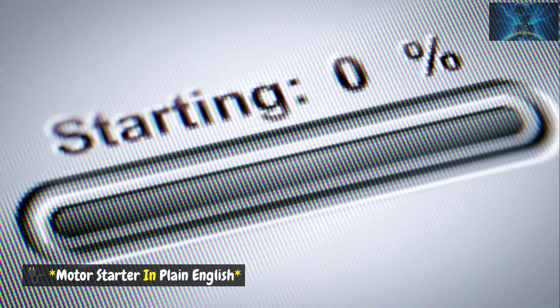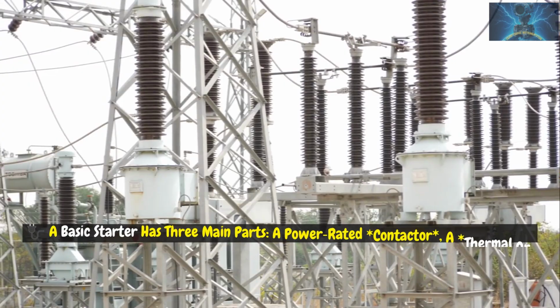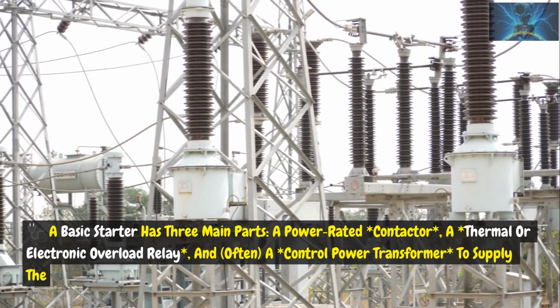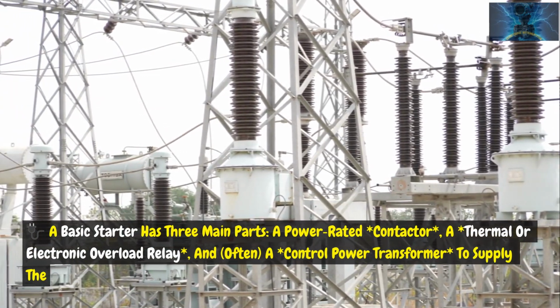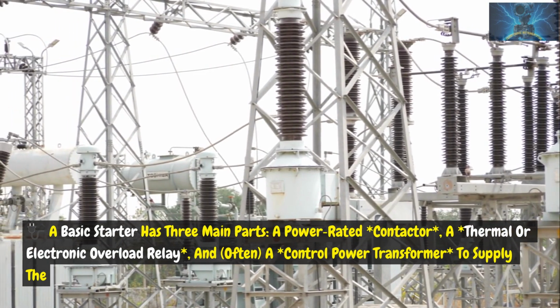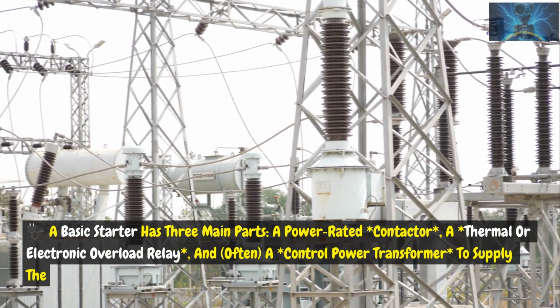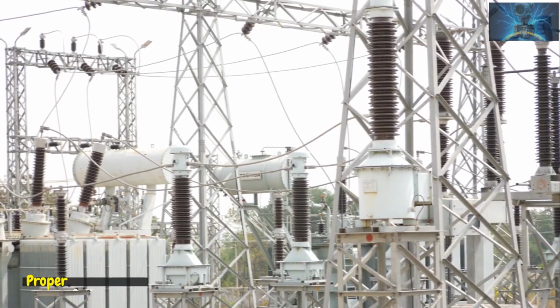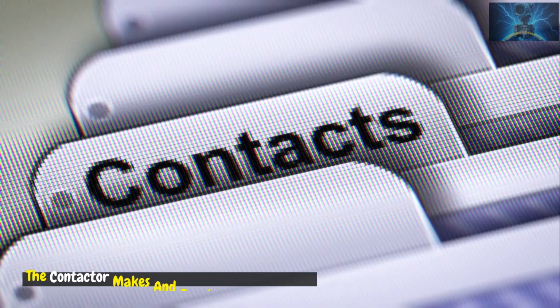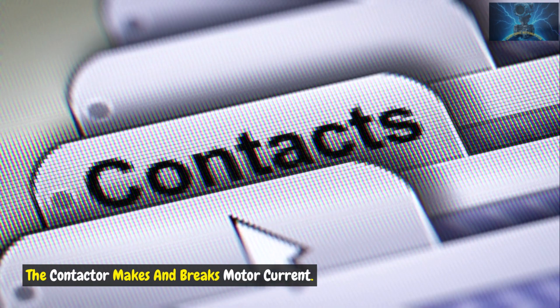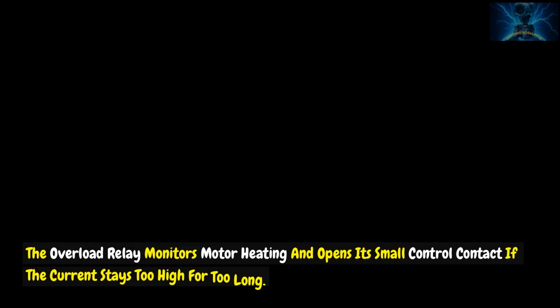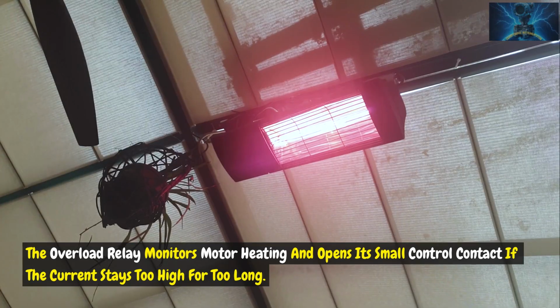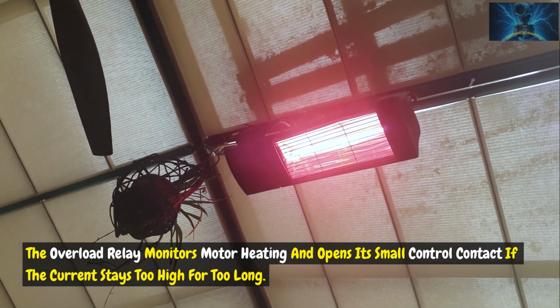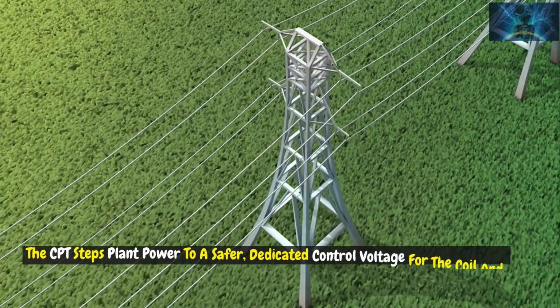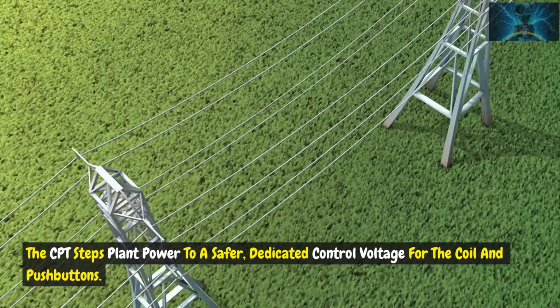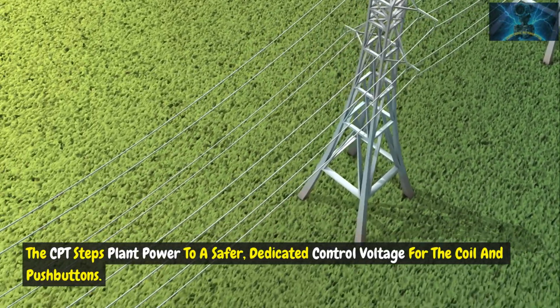Motor starter in plain English. A basic starter has three main parts: a power-rated contactor, a thermal or electronic overload relay, and often a control power transformer to supply the proper coil voltage. The contactor makes and breaks motor current. The overload relay monitors motor heating and opens its small control contact if the current stays too high for too long. The CPT steps plant power to a safer, dedicated control voltage for the coil and push buttons.